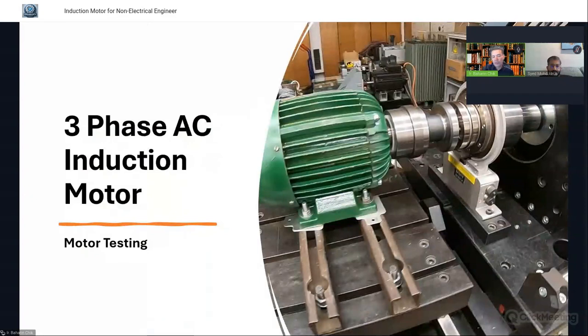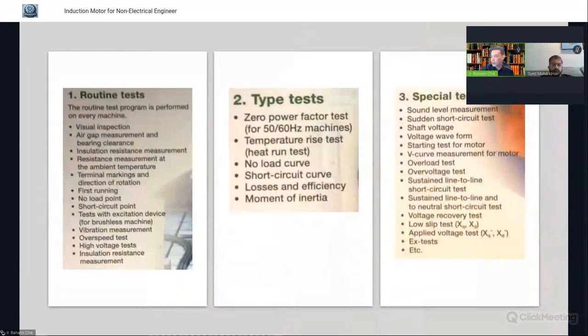Then we send this motor for testing. There are 3 types of testing: the routine test, type test, and special test. Normally these tests are applicable for custom-made motors. But the LV motors are normally standard motors, so we don't need to go through this because they have already been type tested. Only the HV motors, where we need to design for it, need to be tested.